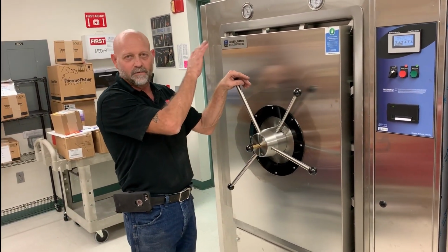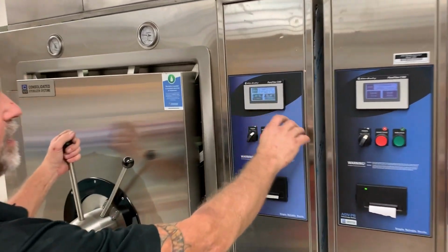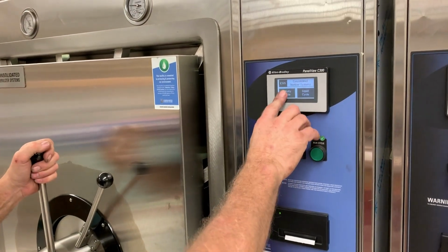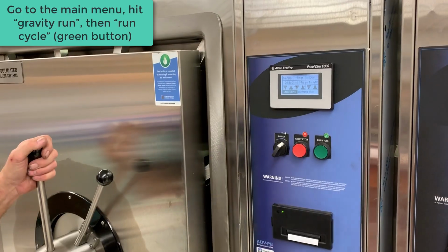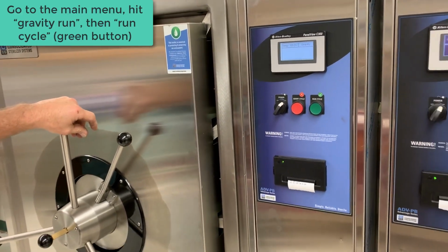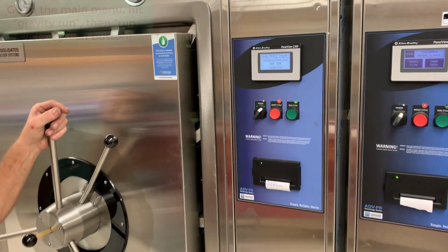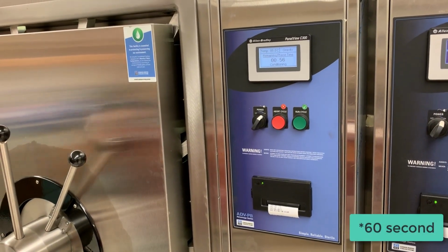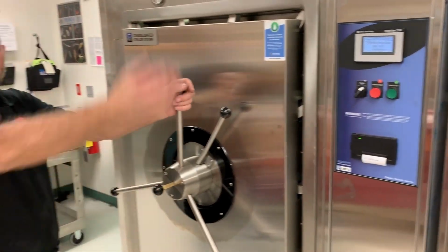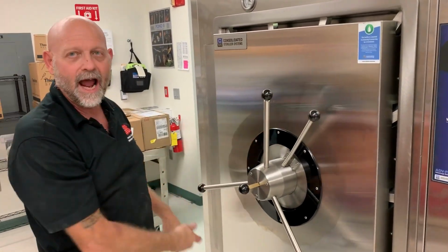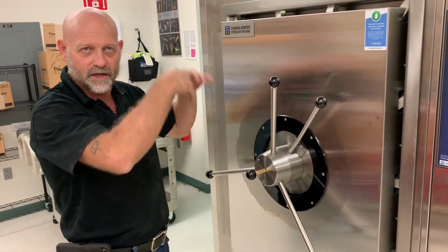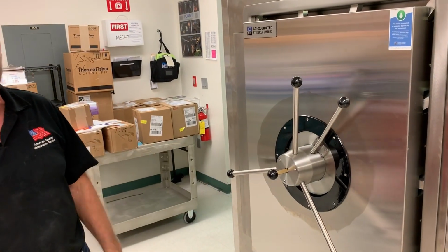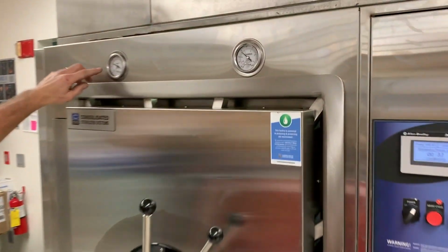The only thing that keeps us from being a bomb is the safeties. Now it's very simple. We go back to the main menu because we've set our run for a gravity run, and what we do is hit run cycle. Okay, what it's going to do now is a 60-minute conditioning. It's just dumping steam through the chamber and out the drain to condition the chamber and bring it up to temperature. You'll notice I've got pressure in the chamber, and you can see where it's pulling pressure from the jacket.